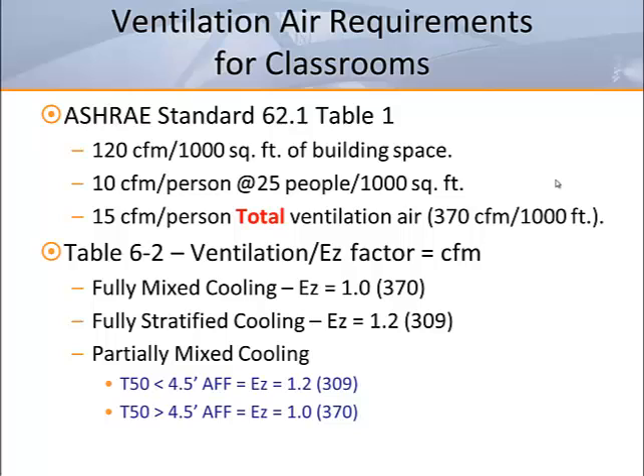The results of ASHRAE Research Project RP 1373 has allowed for a change in EZ per Addenda A of the 2010 standard. For underfloor systems, when the plume of air from an access floor outlet is less than 4.5 feet above the finished floor, at 50 feet per minute terminal velocity, the EZ is now 1.2 or 309 CFM, the same as displacement ventilation. For jets with throw higher than 4.5 feet, the EZ is still 1.0 or 370 CFM is still required.